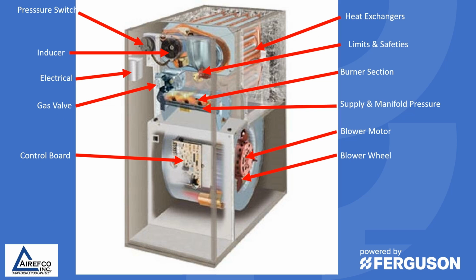The electrical to the furnace, most furnaces need a good ground to operate. So if you have control boards and things that are happening to the furnace that don't make sense, it could very well be that you've lost your ground. So make sure you have a good ground to each one of these furnaces.